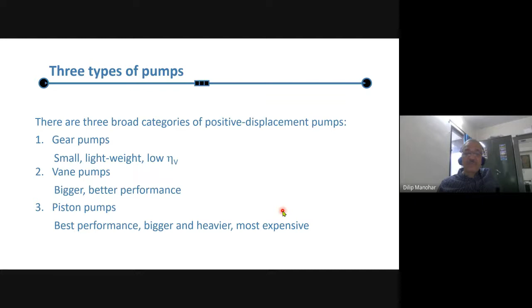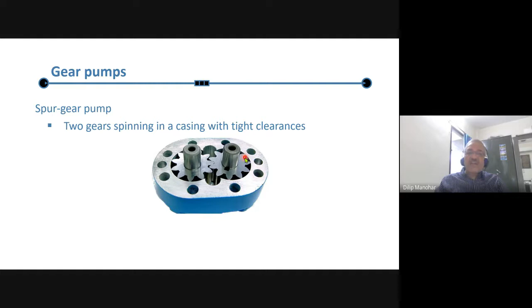Now I'm showing the gear pump design, how the gear pump is constructed. Here there are two gears meshing with each other, and there is an inlet port and an outlet port depending on the direction. The gear has a very small clearance between the casing and the gear. The clearance between the gear OD and the casing ID is almost at the micron level, that means 25 micron, 30 micron, 40 micron. It is not in millimeters, like a clearance of 0.1 or 0.2, and not even 100 micron. It is less than that, about 50 microns. The two gears rotate in a very tight clearance, meaning very low clearance.